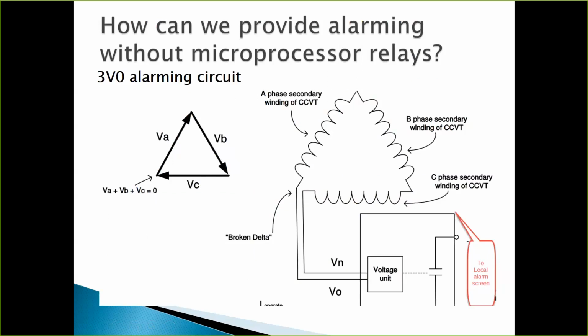If we have electromechanical relays, typically the windings of the CVT have one winding that feeds your protection, another winding that may feed your backup protection, and a third winding that goes unused. You can take that third winding on each phase and configure it into what I call a broken delta. You take one winding from each phase, series them together, break that delta right there, and install a relay. Set it for 10 volts, with an output to alarm your local screen. As long as VA, VB, and VC are alike, we have nothing. But if we lose the capacitor stack in VA, the voltage could go up or go down. Now we have a current flowing in that delta, and that current provides a voltage across that relay. It picks up an alarm.